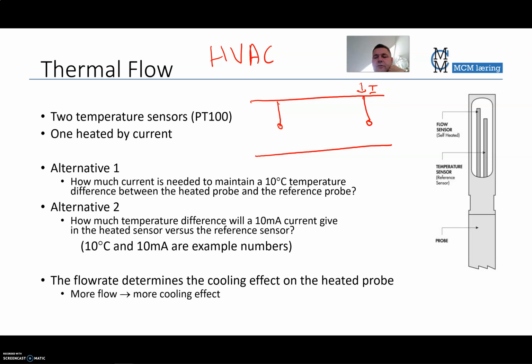If you have a constant current, you would expect a constant temperature difference between the two. But if you have a flow, you will have more cooling effect on that one, and therefore the temperature difference goes down. So the temperature difference between the normal PT100 and the heated PT100 depends on the flow.